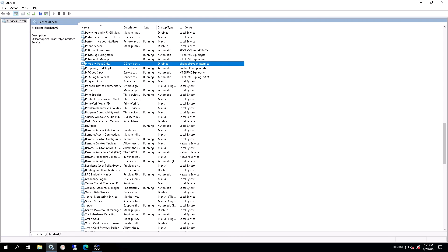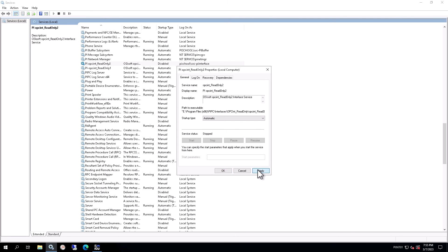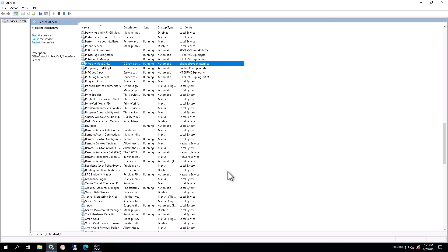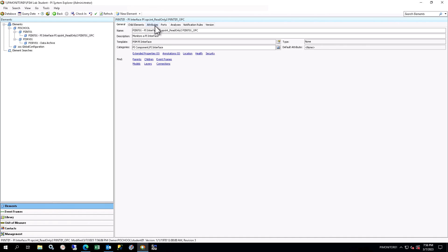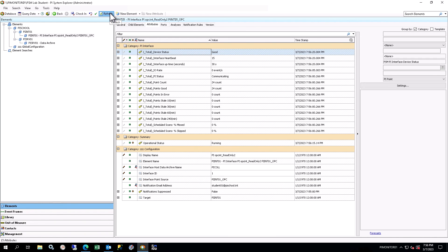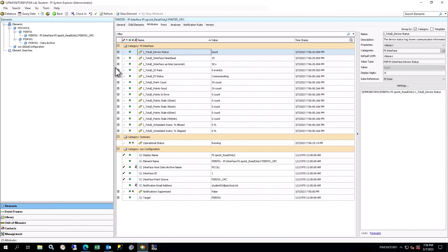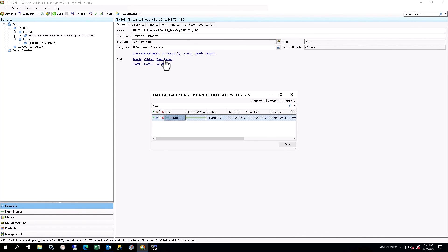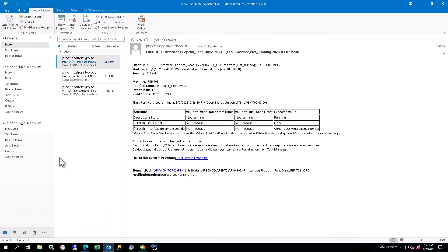Return to PI In 01. On PI In 01, open the Windows Services pane. Find the service that matches the display name for the Interface Instance and change the startup type back to Automatic. Click Apply and then click Start to start the service. Click OK to close the window. Ensure the status changes to Running — you may need to click the Refresh button to see this. Now return to PI Monitor 01. In the PI System Explorer, in the Attributes tab, check the values of the Total Interface Uptime Seconds and Operational Status attributes. They should change back to good values. You may have to refresh and wait a few minutes for the interface to connect and start sending data. Select the General tab and click Event Frames. Confirm that the Event Frame has closed — it will now have an end time. You should also receive an email in Outlook indicating the event has closed.